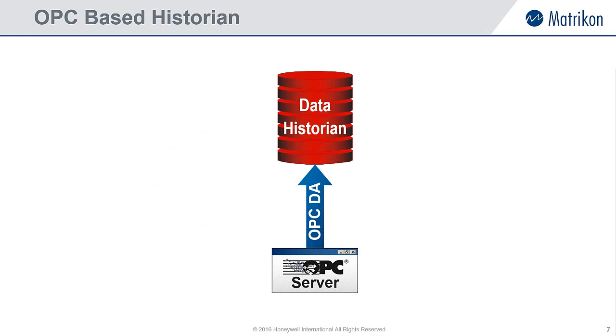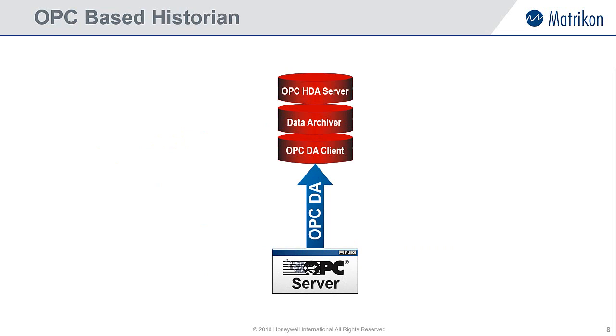So how does it work? Let's take a closer look at an OPC-based data historian. The OPC-based data historian contains three key components. Firstly, an OPC-DA client, which enables the historian to connect to OPC-DA servers in order to collect real-time data. The next piece is the archiver or core component, which is responsible for taking the collected data and storing it to disk. And lastly, an OPC-HDA server, which allows external OPC-HDA enabled tools to connect to the data archive and access the stored data.